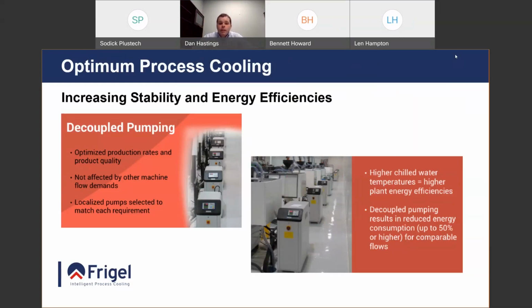Also, by decoupling from a central chiller system, perhaps you have that one machine at the very far end of the room, the last machine on the piping system, where it's just not getting a lot of flow and pressure because it's all the way at the end. The other machines are stealing the flow and pressure from the central chiller, and the one at the end is getting left out. By putting a booster pump, a chiller, or a TCU on that, we can provide the right flow and pressure that tool needs.